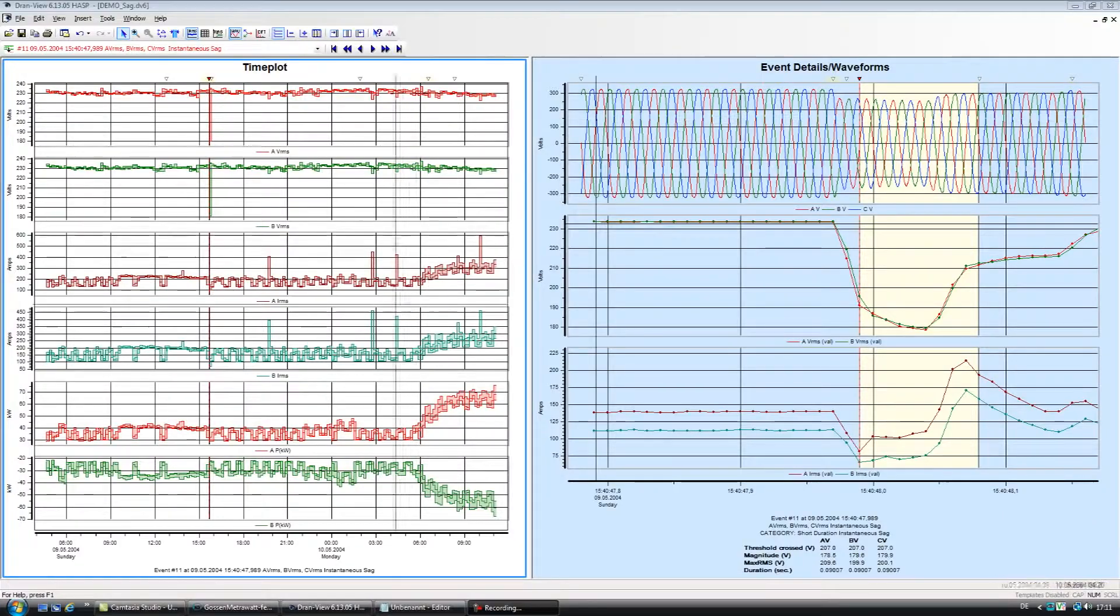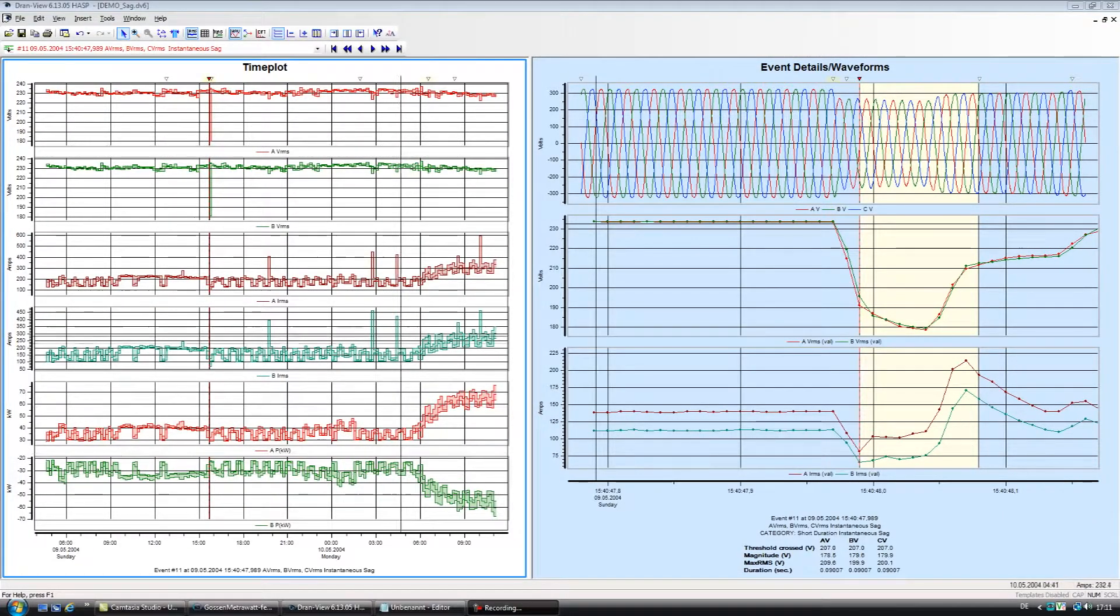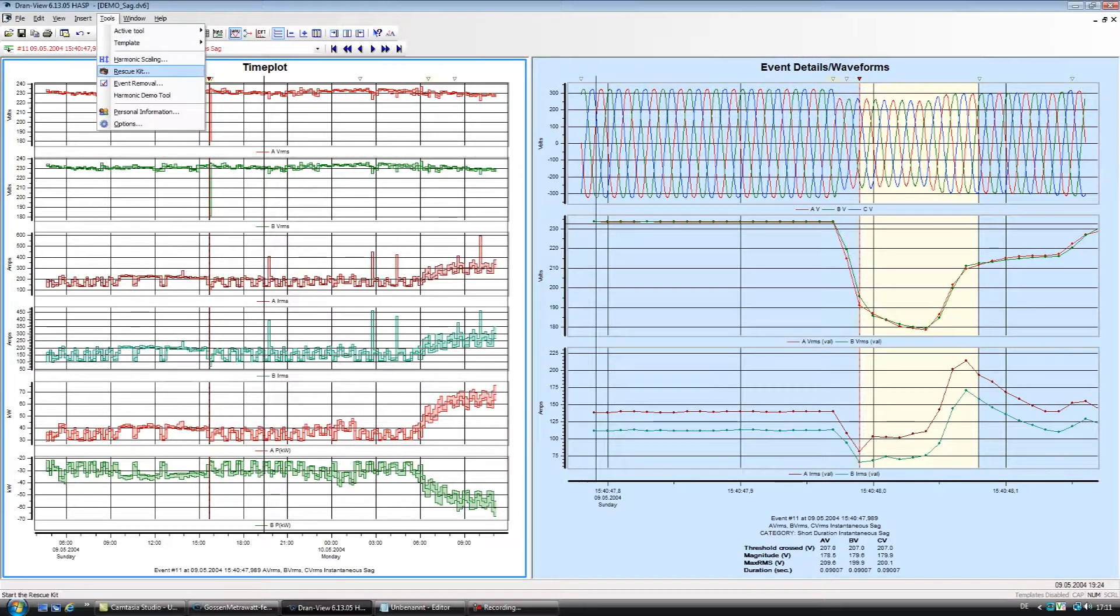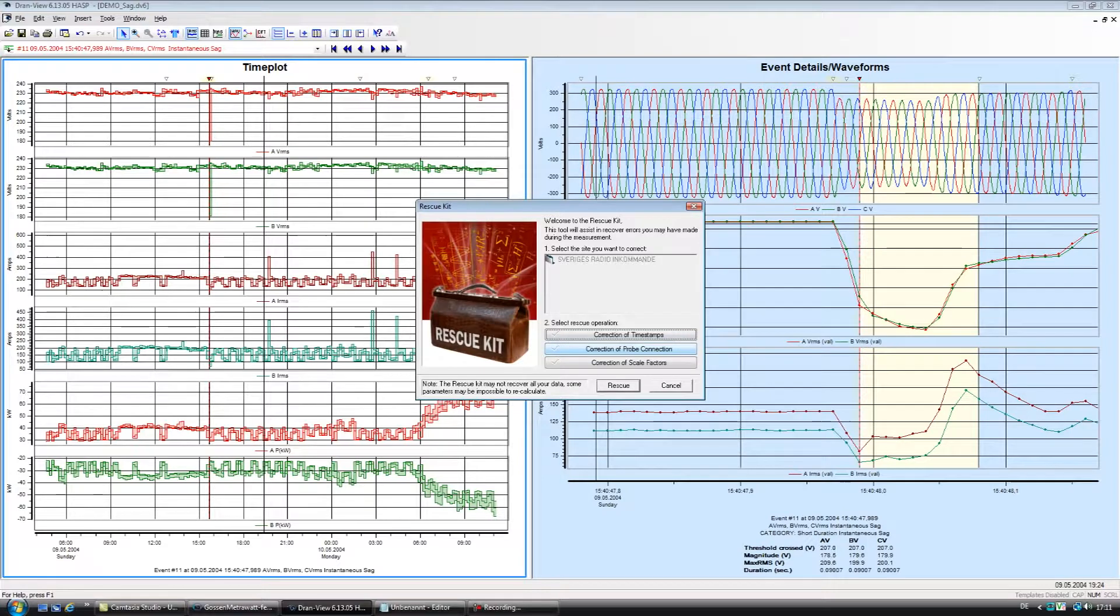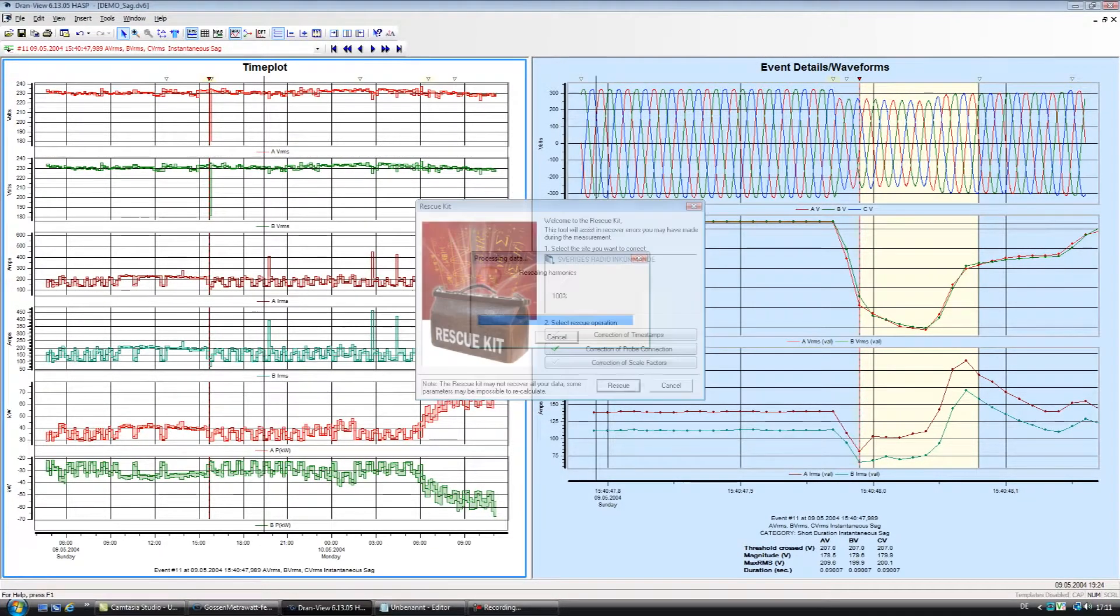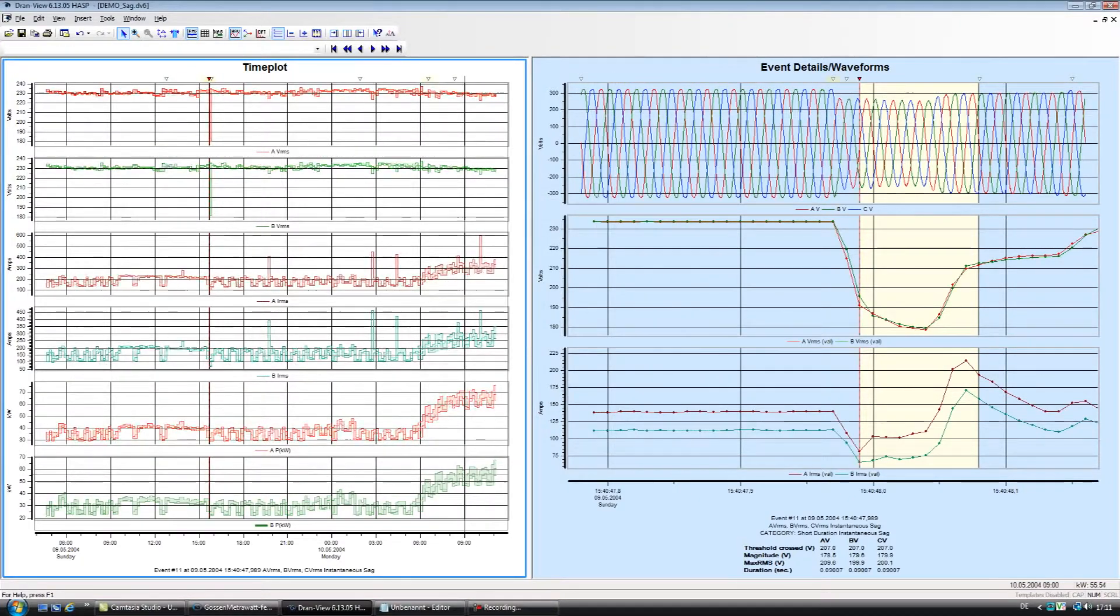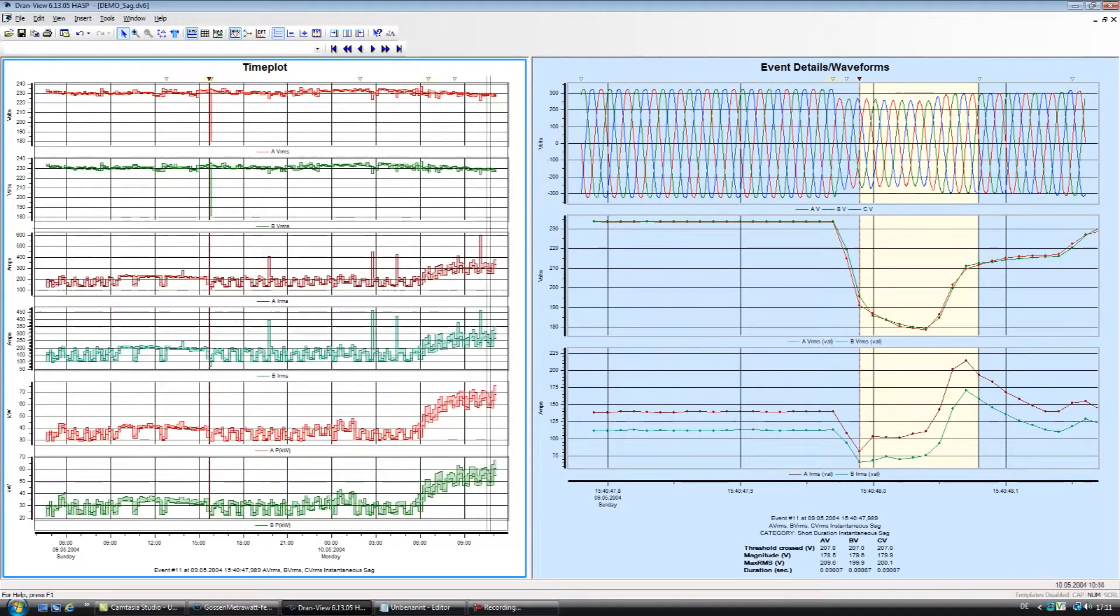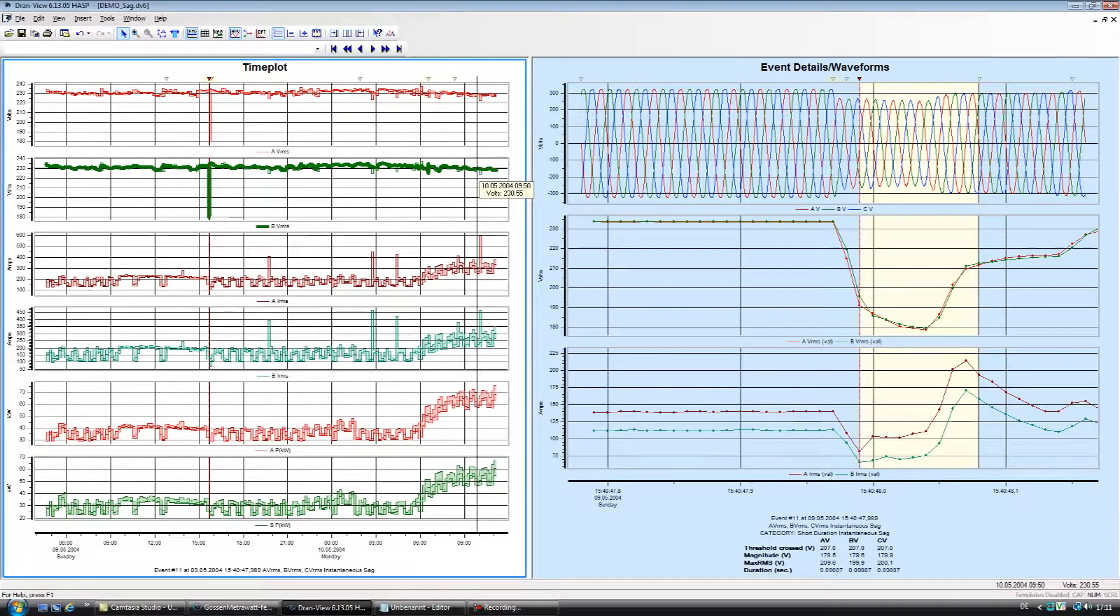Rescue kit. Have you ever finished a power survey then realized you had a CT connected backwards, the instrument time was wrong or had another human error? Dran-View's rescue kit can undo some common mistakes made during your survey. Not all errors can be fixed, but the rescue kit can fix items such as inverted current probes, improper scale factors and the wrong time.